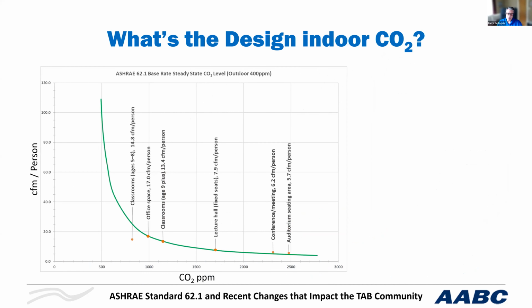All right. So steady state value is just that. And when you look at ASHRAE 62, when 62-2004 came out, or actually Addendum n to 62-2001, they separated the occupant area ventilation rate and the area ventilation rate. So it's two different values, which really made the calculation of steady state a lot more complex than it used to be. But what I've done on this chart is combine that occupant plus area rate. It's on the y-axis as CFM per person. And this curve reflects where the ventilation rates in Table 6.1 intersect on that line, and what the corresponding CO2 parts per million is below the steady state.